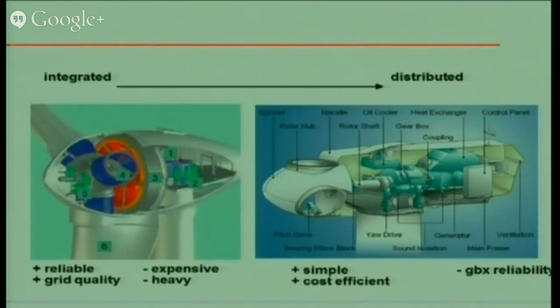There is a necessity to first generate AC, alternating current, then convert it to DC using thyristors and IGBTs and inverters, etc., and then convert back to AC. That final stage of AC conversion is what connects to the grid. AC, DC, AC—there is so much electronics in this. Power handling is very high, but there is no gearbox.